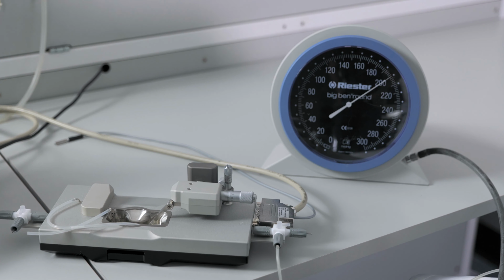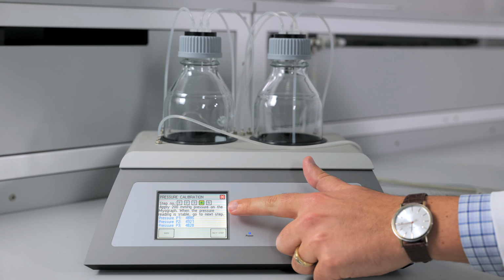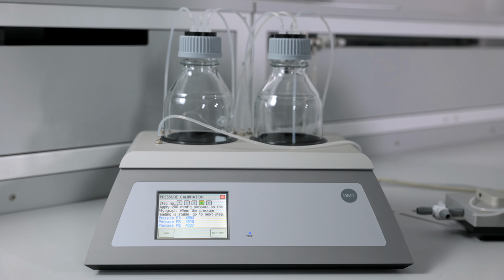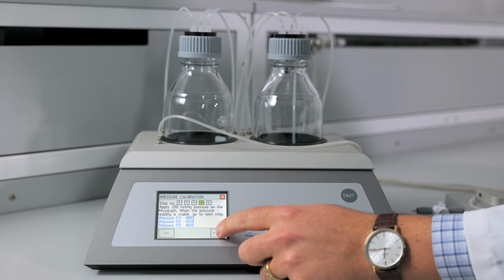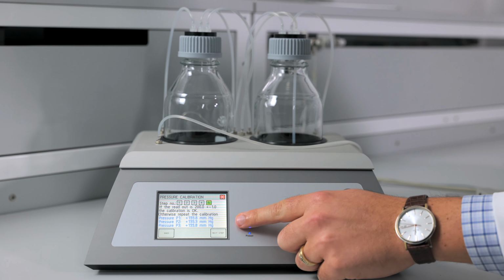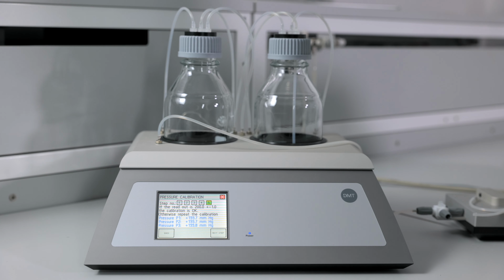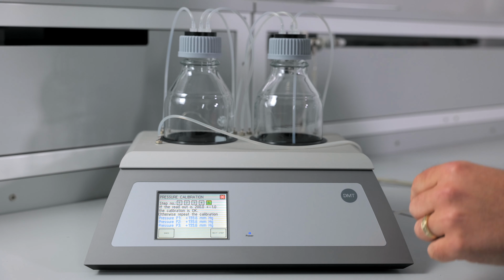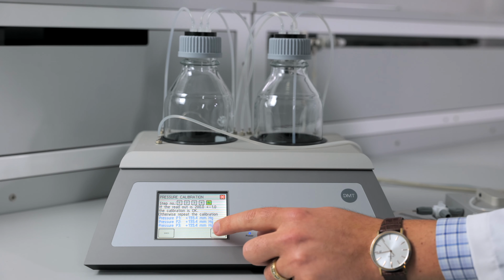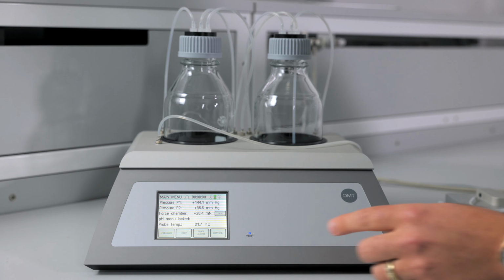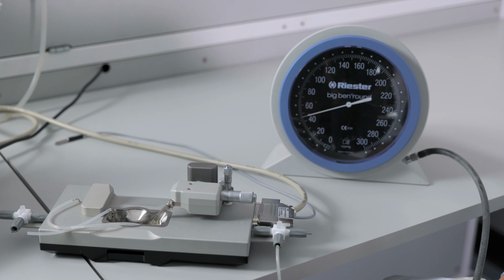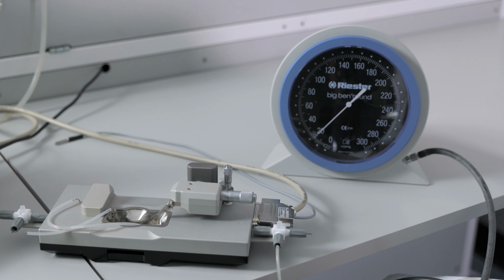Pressure is holding again. You can see our pressure readings have all increased again. We can hit next step. The final step is ensuring that each reading is approximately 200 millimeters of mercury. You can see all are around that number. So we finalize with the next step, and pressure is now released internally. But that concludes the pressure calibration.